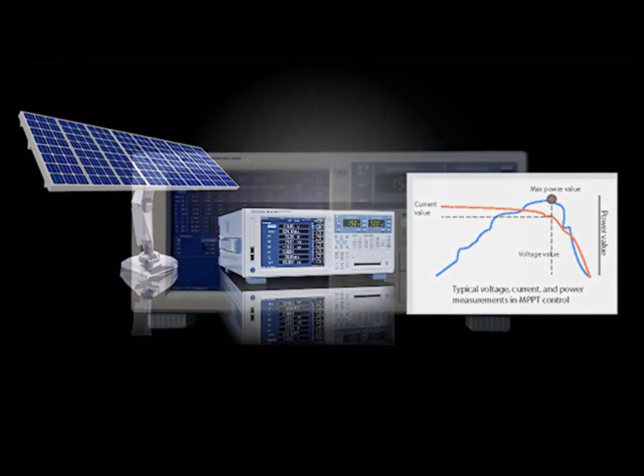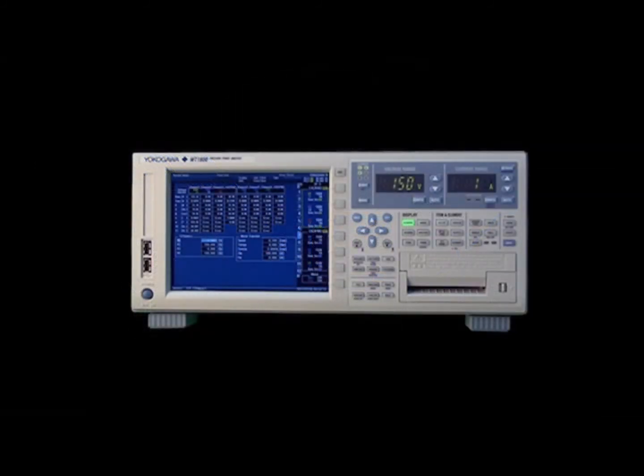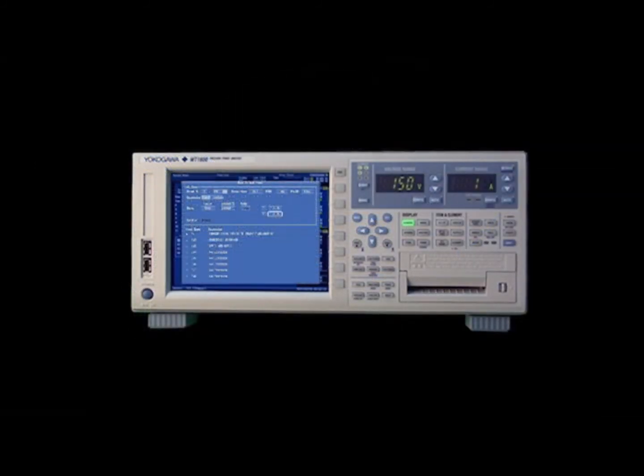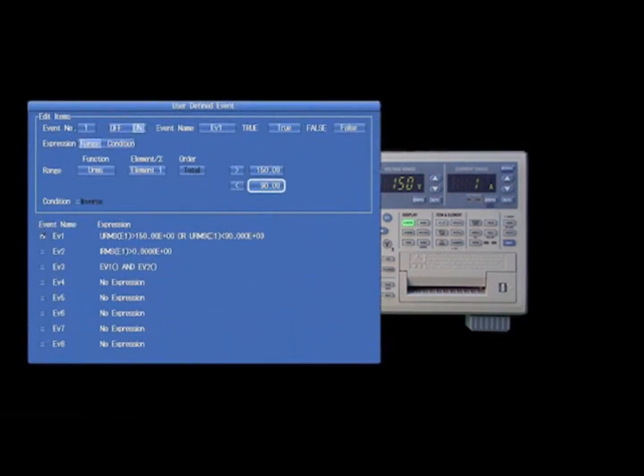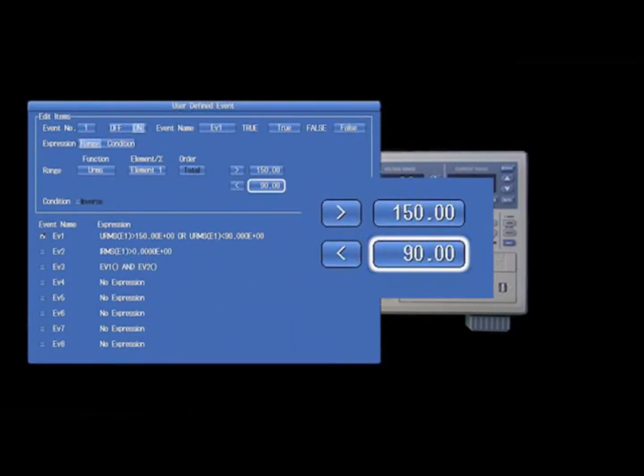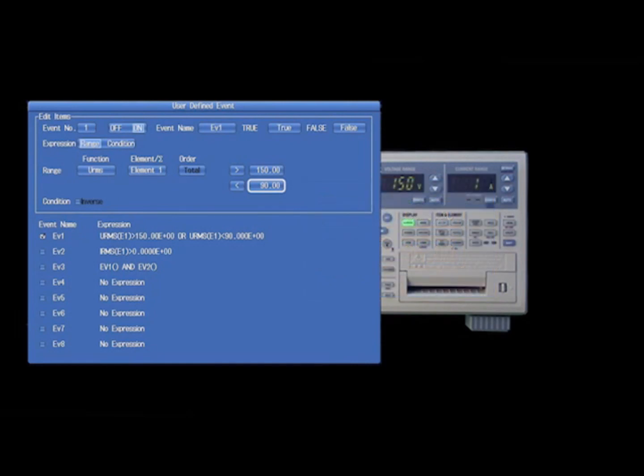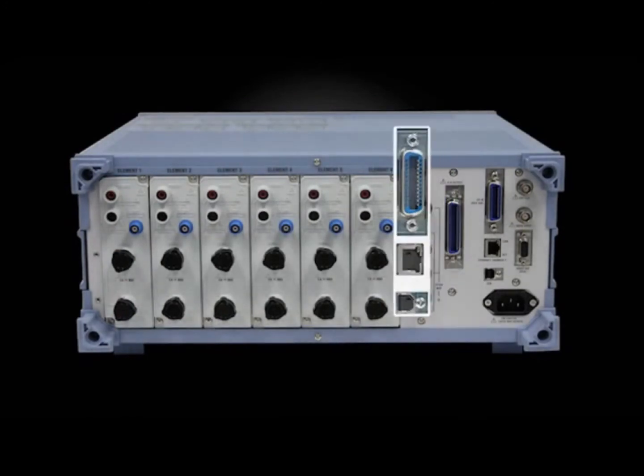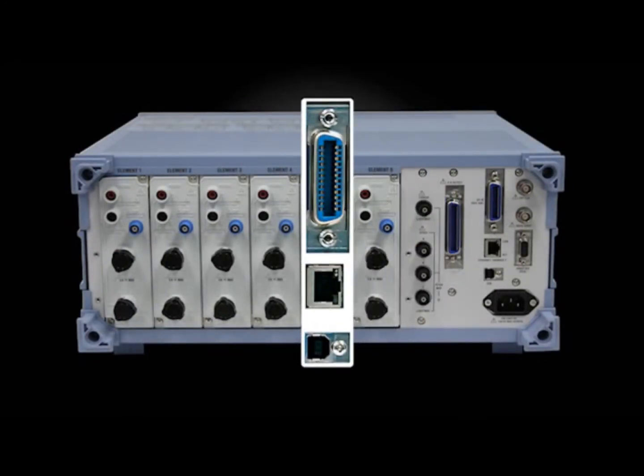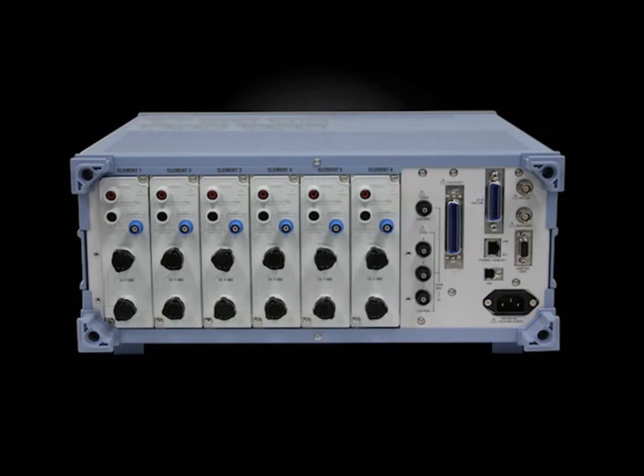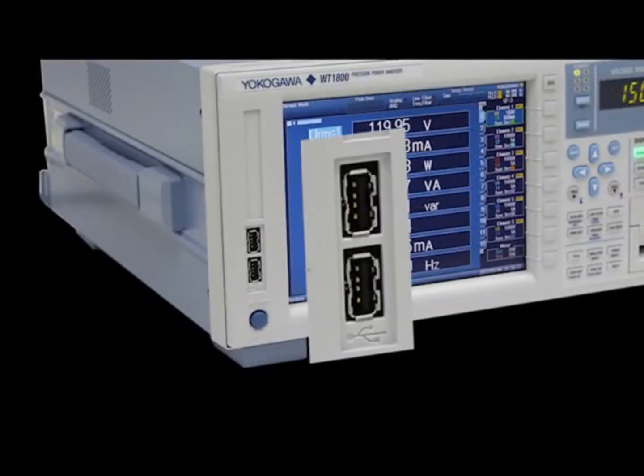fluctuates greatly. For the first time in the high-precision power analyzer industry, an event trigger function is available to capture a particular event. A trigger can be set for measured values that fall out of a pre-selected range. The WT1800 can then store, print, or save the data that meets the trigger condition. The latest communication interface ports such as Ethernet, USB, and GPIB are all included in the WT1800. Plus, support for USB removable storage media is also provided.